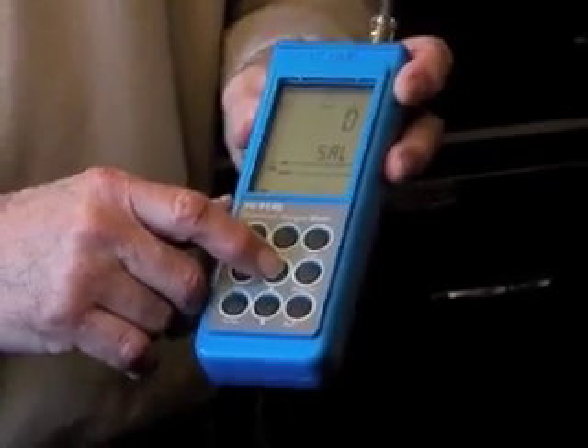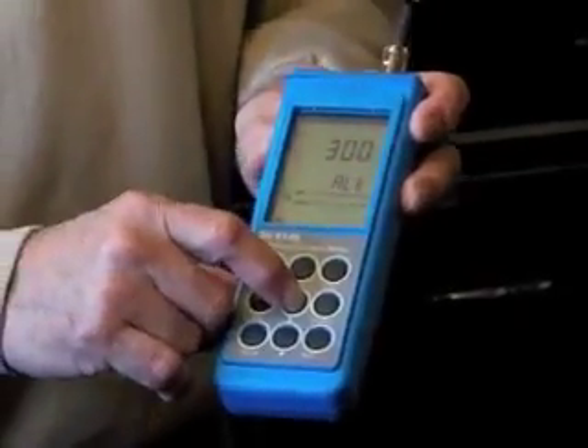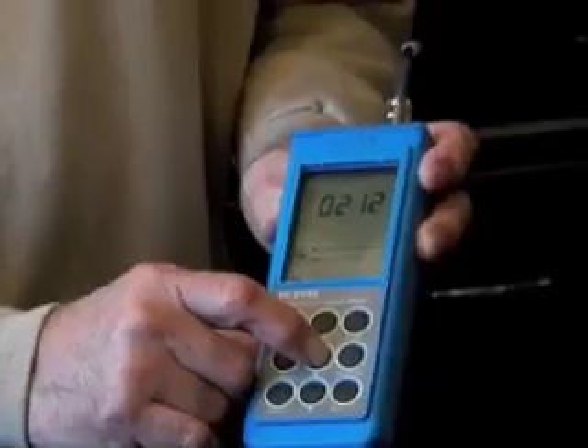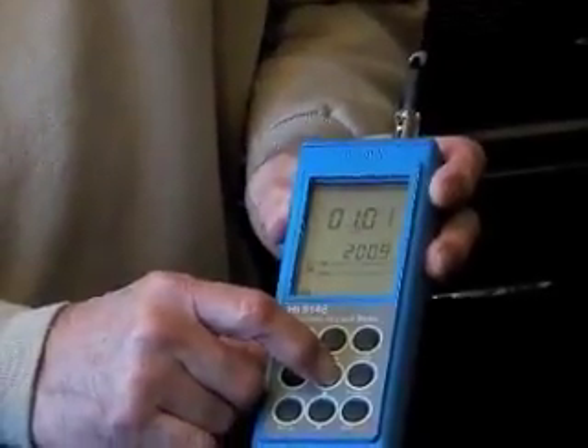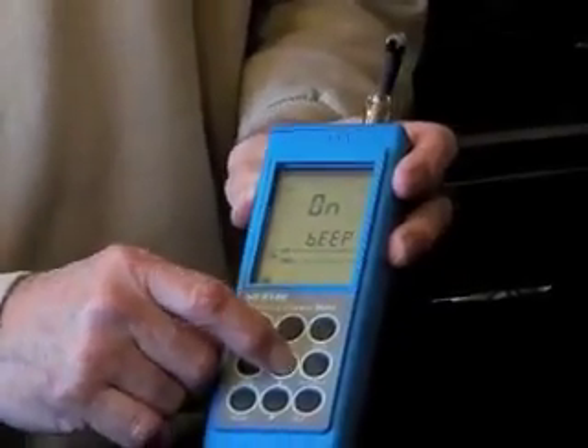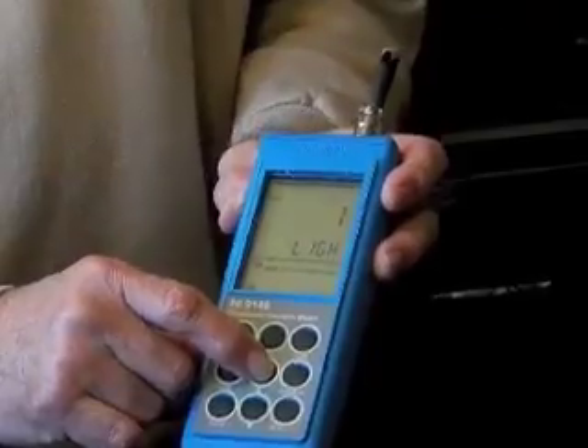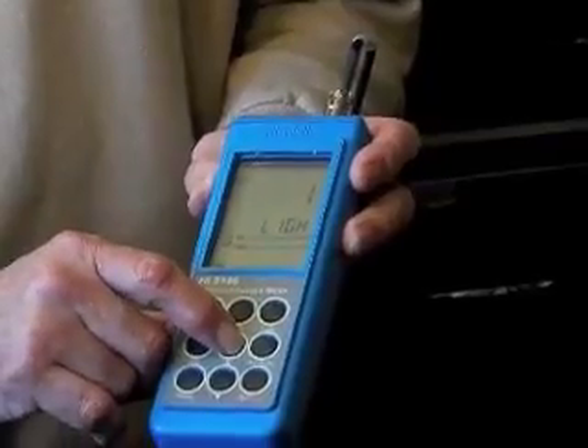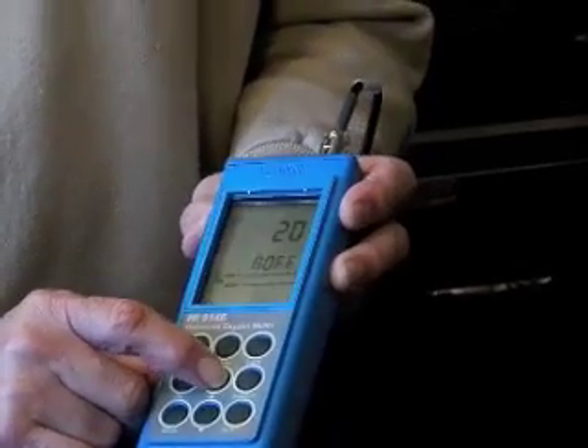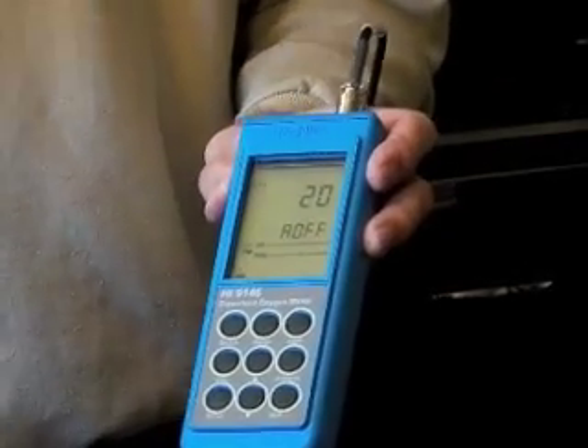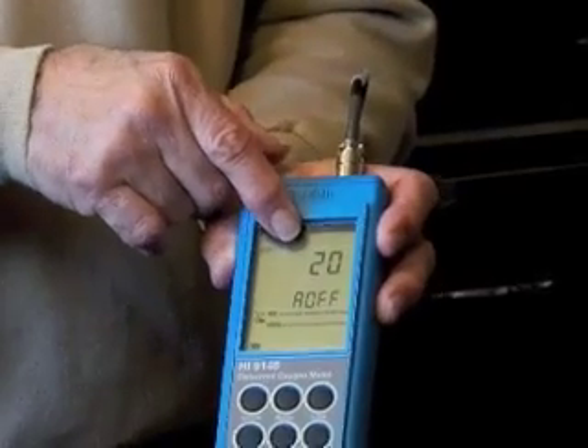So you hit that, and like when we were changing altitude, it has salinity, and you want to just use the arrow up or down button to cycle through. Next would be altitude. Then you're going to get some time and date type features here. And then there's a beep. You can have it beep when there's something wrong, and that's turned on. That's okay. Then you get a backlight feature. It's the intensity of the backlight, and it's set at 1 so that you're not using up battery. And then here's A off. That's the auto off feature, and you can see it was set to 20 minutes.